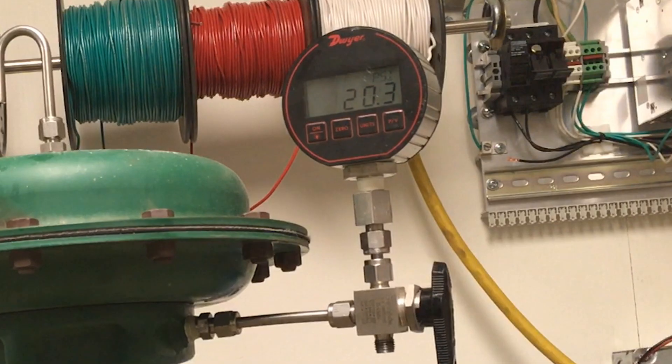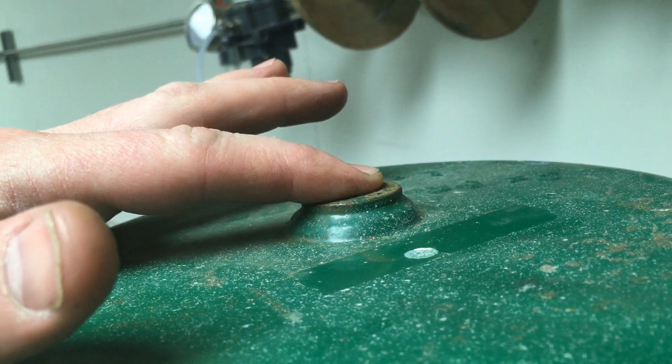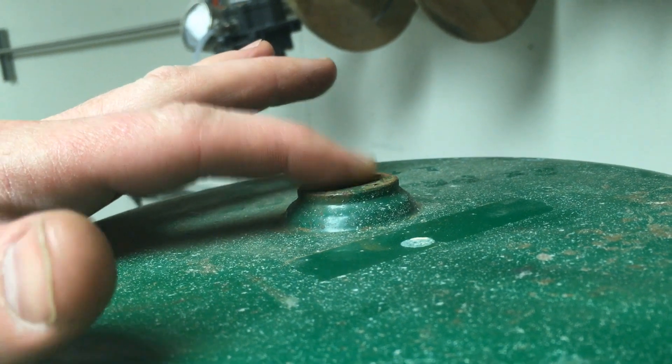If you notice the pressure gauge dropping during the pressure test, you can remove the vent from the top and place your finger over the hole to determine if air is passing through the diaphragm.